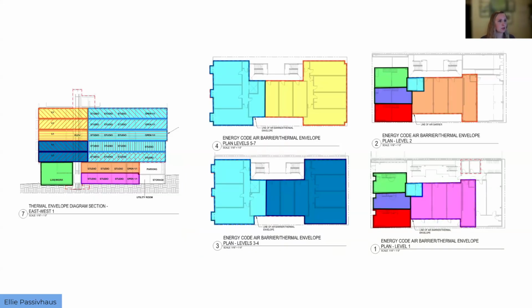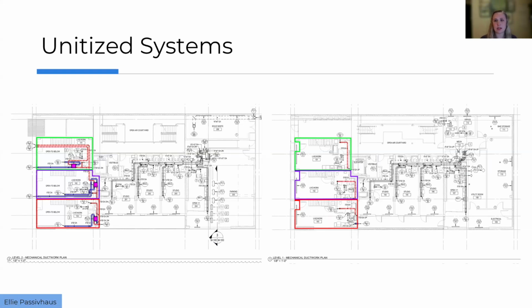So here's how these zones were broken up. For levels 1 and 2, you have the green, purple, and red that show the individual units for those live workspaces. And then from that point on, it's basically floor by floor, usually serviced by 1 to 2 HRVs. So as you get further up in the building, basically an east and a west zone. So again, the live-work units each had their own individual HRV in the bathroom ceiling of the lofted portion of the space. A consideration for that is one of the supply diffusers, you can see over here on the left, was difficult to reach in that it was at the top of this lofted ceiling space, which made it difficult to get up and verify the airflow for.